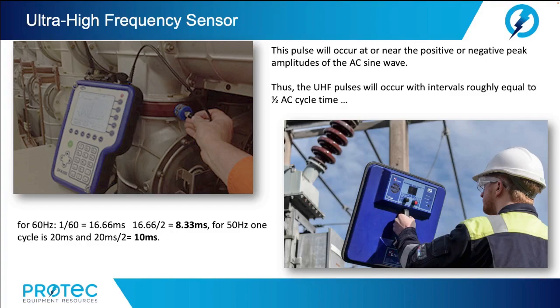To prove that UHF could be from a PD activity, we can show that there is a 180-degree separation, 8.33 milliseconds or 10 milliseconds, between the UHF pulses. This is a function of time-resolved or phase-resolved measurements. These phase-resolved measurements are made in real time and serve as the basis for quick partial discharge detection in the field.